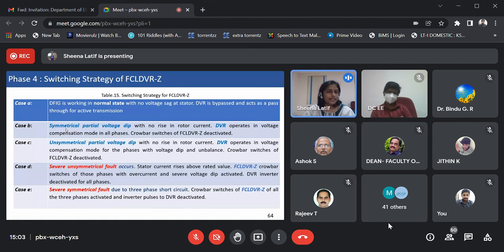The switching strategy for FCL DVR impedance has 5 different cases. In the first case, the DVR is working in the normal operating mode with no voltage sag. Hence, the DVR and FCL DVR will be bypassed. Whereas in the case of symmetrical partial voltage dip or unsymmetrical partial voltage dip conditions, the FCL crowbars will be deactivated and the DVR mode will be activated in order to assure a partial voltage restoration.